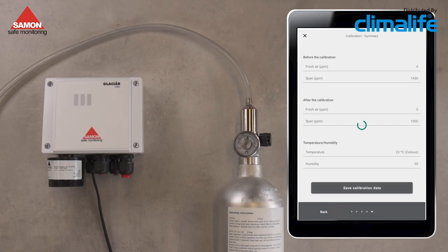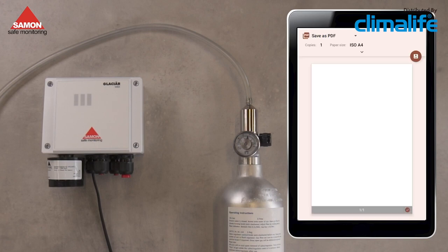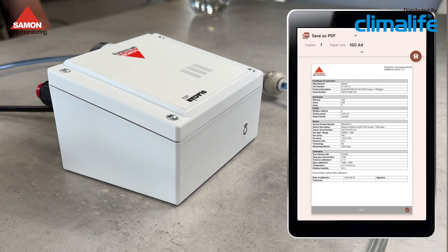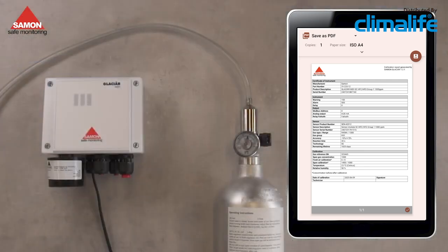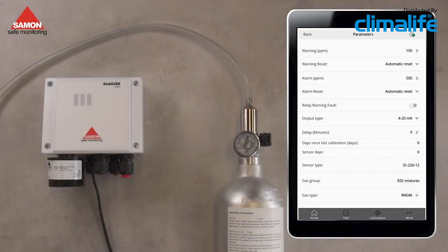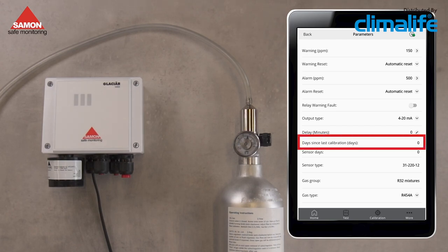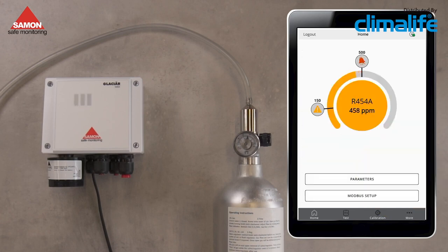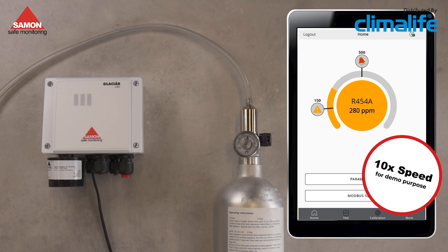Save the calibration report. Use File Manager to save it as a PDF file, or you can share the calibration report via email. Correct completion of the calibration process can be verified by checking that the value of days since last calibration has been updated to 0. Make sure that the sensor value has stabilized at normal levels before disconnecting the app. If the value has not stabilized, there is a risk of setting off an alarm.